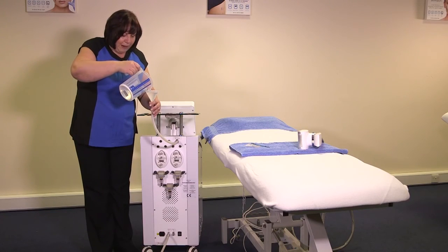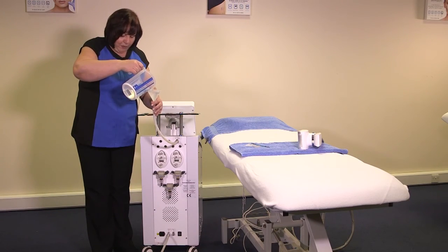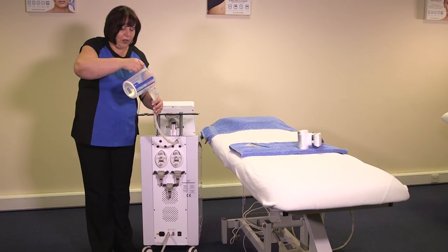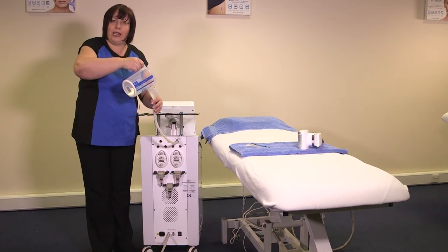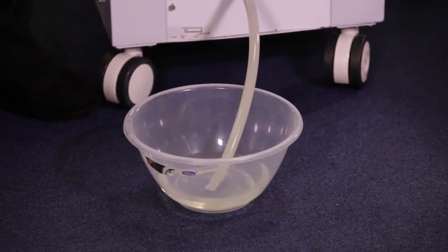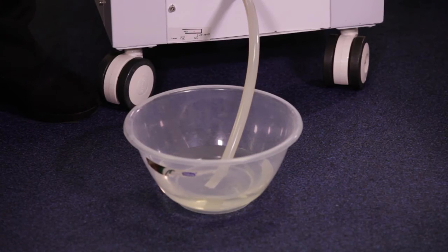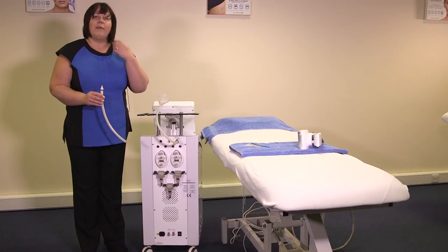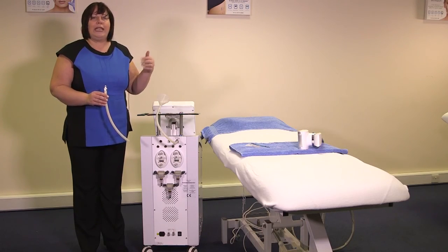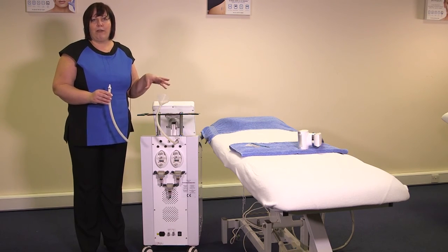When you've got the same amount of water coming out from the exhaust hole tube that you've got going in at the top, you know then that your tank is full. If out of the exhaust hole you've got lots of bubbles and lots of an inconsistent flow, then you must make sure you keep filling until exactly the same flow is coming out from the bottom as going in at the top. We do recommend then that every 3 months your unit is completely drained and refilled with fresh water.